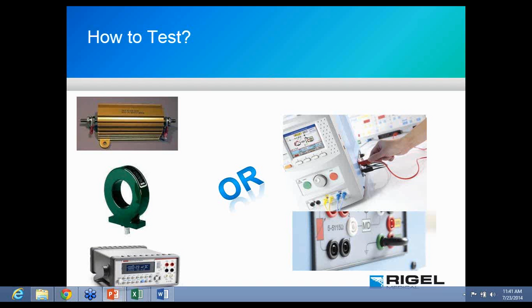Remember that the manufacturers specify that you test with active electrode open and neutral electrode open. So again, I bring this back up. This is what Valleylab tells us to do. You can connect a transformer, or this image shows the Unitherm. That black banana cable is coming directly from either the active electrode or the dispersive electrode. You have to test both, and it follows through the white. There's a direct connection there. If you want to look at waveforms, that's how I got them, by plugging into the scope output there.